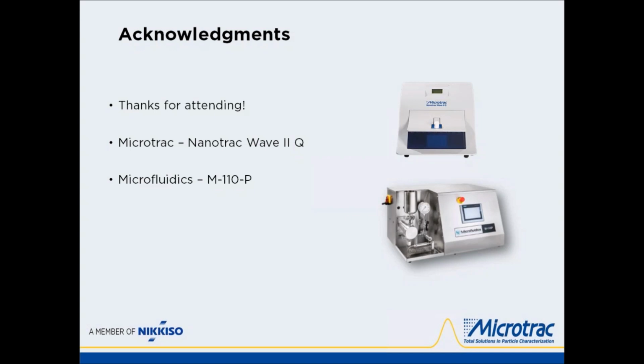Thanks, Tim. So for our next question, what is involved in the cleaning and maintenance of the microfluidics machines? I'll take that one, Tim. It's a good question. So all machines have the capability of doing clean in place. You can run water, a detergent, alcohol through it to clean it. It's really up to the customer for their cleaning protocols. We can make some sort of recommendations, but we won't ever say this is it, because it's a lot of formulation dependent and what they are actually processing. We recommend a PM service annually just to clean up the machine and make sure everything is running smoothly. Maintenance is super easy. Takes mainly cleaning and then changing out a couple pieces here and there every once in a while, but that's pretty much all it is.